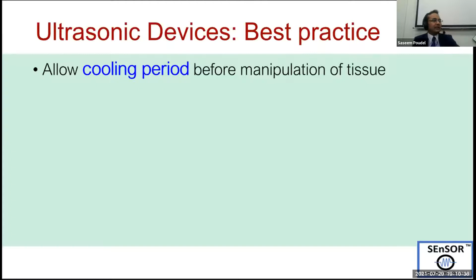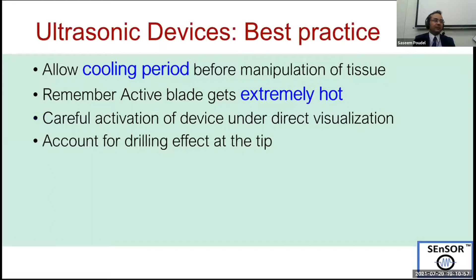On ultrasonic devices, I cannot repeat this more often. This is a very important thing. You need to allow for a cooling period before manipulation of tissue. Remember that the active blade gets extremely hot. It can go well over 200 degrees Celsius. And activate the device carefully, only under direct visualization. You need to see where your active blade is, and account for the drilling effect of the tip, and also lateral thermal spread, as Dr. Sudhit showed.